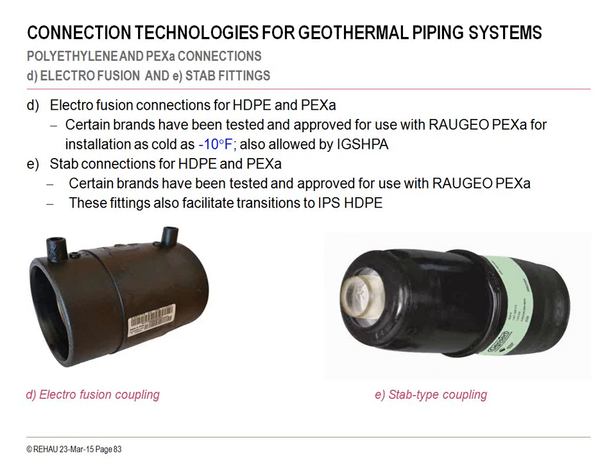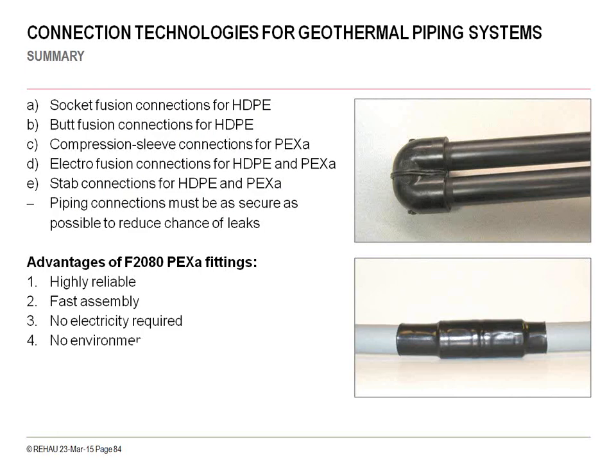On the electrofusion coupling, there are wired elements on either side, and there's a positive and negative pole. There's a machine that's going to be putting voltage and current to that fitting, and it's going to be molding around the PEX-A pipe to secure the joint. There's a barcode there that gets scanned so the machine knows how much to apply and for how long. It takes the guesswork out of it. So in summary on the connections, HDPE is generally done with heat fusion. Again, the stab and electrofusion fittings are applicable for the HDPE pipe as well as the PEX-A pipe. And then there's the cold compression fitting systems that I've mentioned that's supplied by RAUGEO. And again, it's very fast, and the skill level is very low. It's a one-man process.